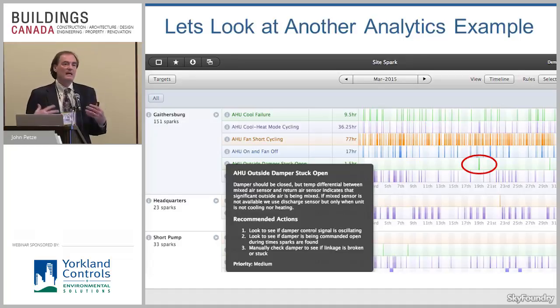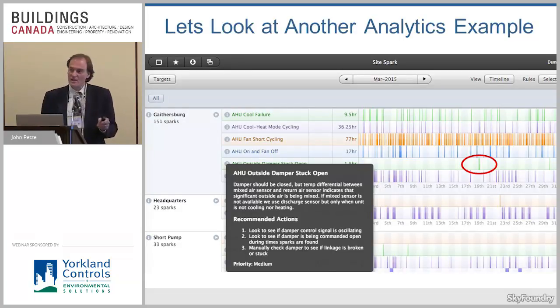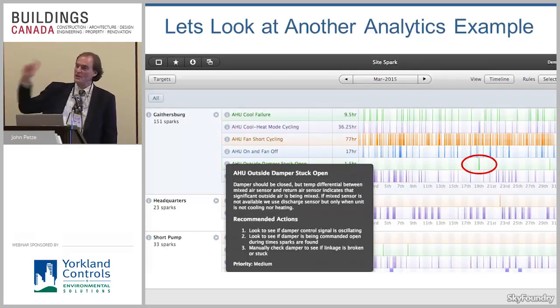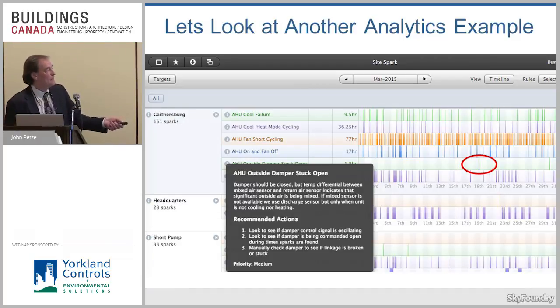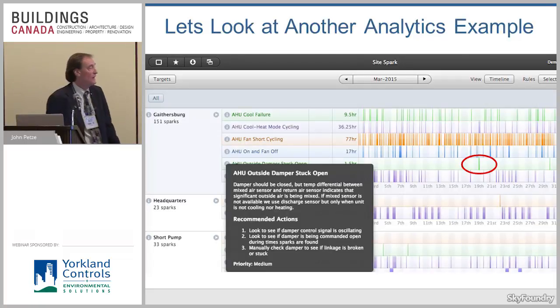So one of the key things about analytics is how do we engage the operator, how do we help people resolve issues. A simple tool is just descriptive information. When a rule triggers, it also says, hey, here's what was found. The damper should be closed. I was looking for the closed condition, but the temperature differential between the mixed air sensor and the return air sensor is exhibiting a pattern that can't possibly happen unless the damper is open. You may think it's closed. You commanded it closed. The signal says it's closed. It ain't closed. Okay? And it detected that pattern, and it can even go on to recommended actions, right?